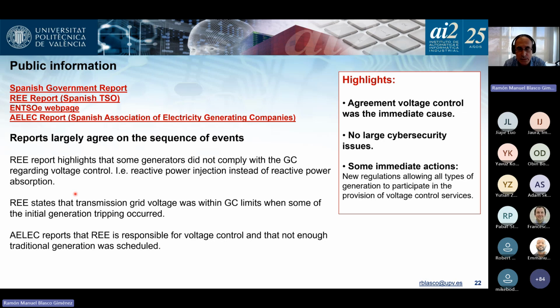Some PV plants have been singled out as probably the cause of the initial oscillations. The owner is not happy and is contesting that. And the generating association is pointing at the TSO as responsible for voltage control. Damages are anything between 2 to 2.5 billion euros. But it's nice that you have the reports so you can have a look at that. Regretfully, the first two and the last one are in Spanish. You can use automatic translation, but take care because some of the technical nuances are lost in automatic translation.